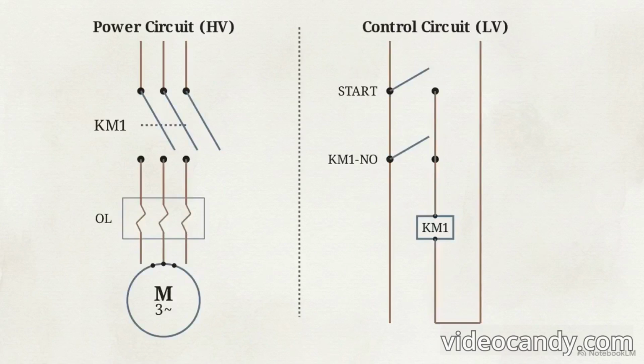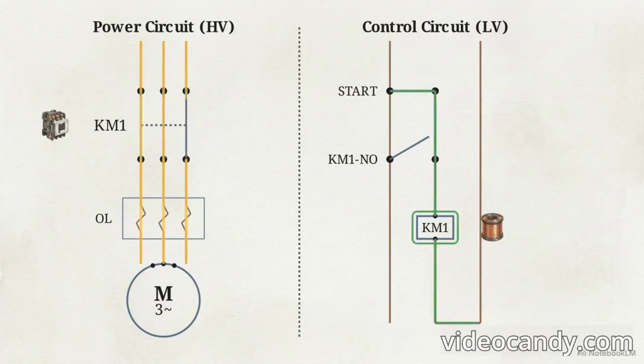We can trace exactly how these physical components and logical modules interact by examining the fundamental direct online, or DOL starter. This schematic displays the standard DOL layout, separating the high-voltage three-phase power circuit on the left from the low-voltage control circuit on the right. The high power path runs straight down through the contactor's three main poles, passes through the thermal overload relay, and feeds directly into the motor.